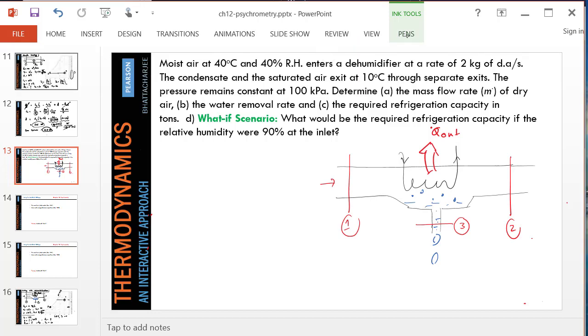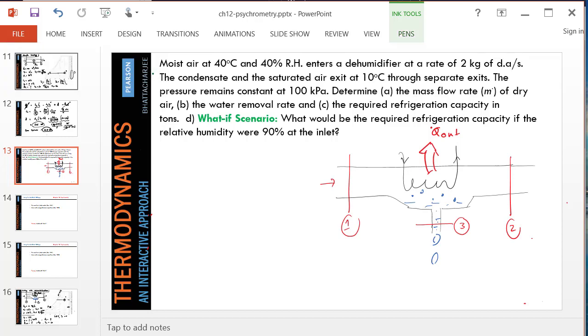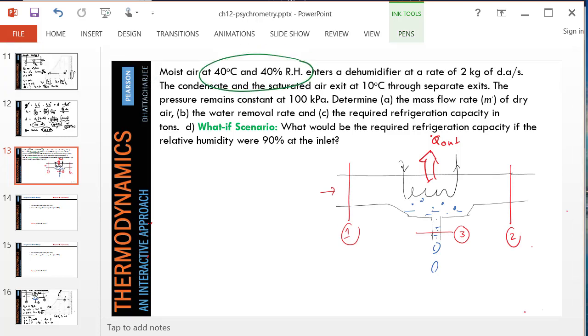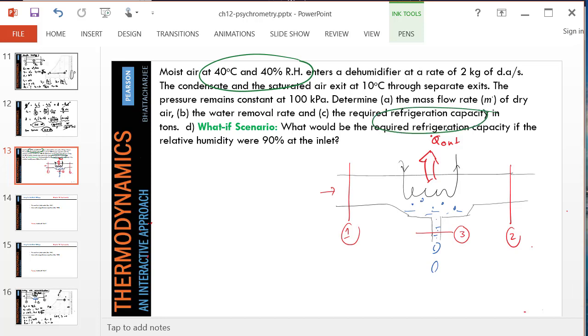As you can see, moist air is entering at 40 degrees Celsius, 40% RH. And then it's cooled. Heat is being removed with a cooling coil. Q.out is one of our desired variables. We want to figure out how much is the refrigeration capacity, which means what is Q.out. Also, we would like to know how much water is condensed, taken out of this air.